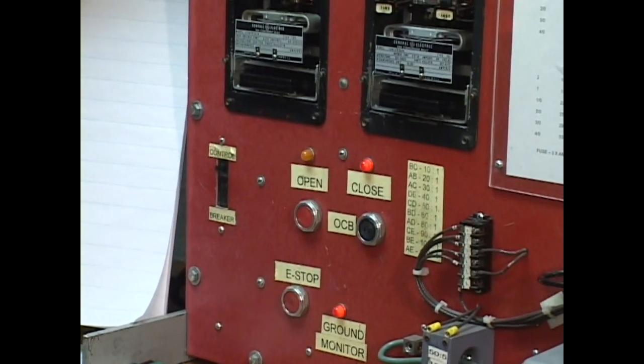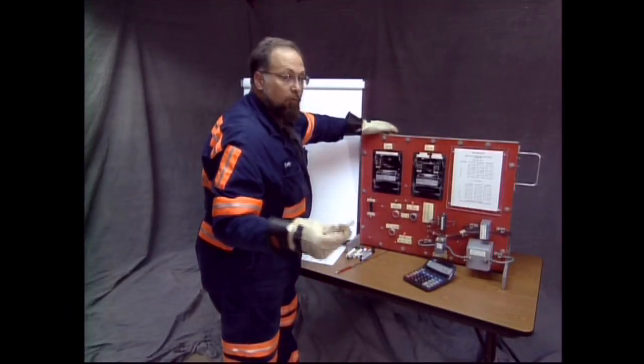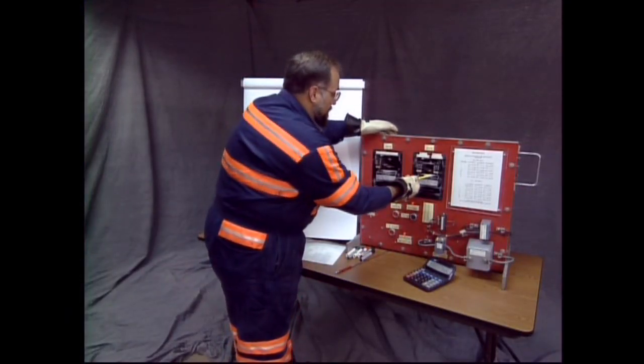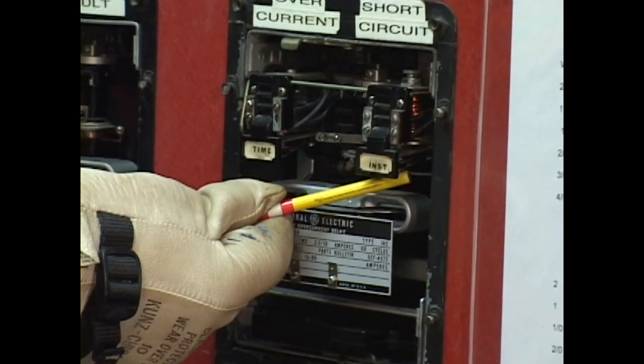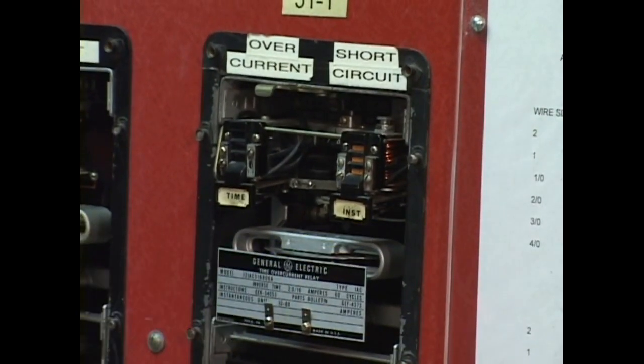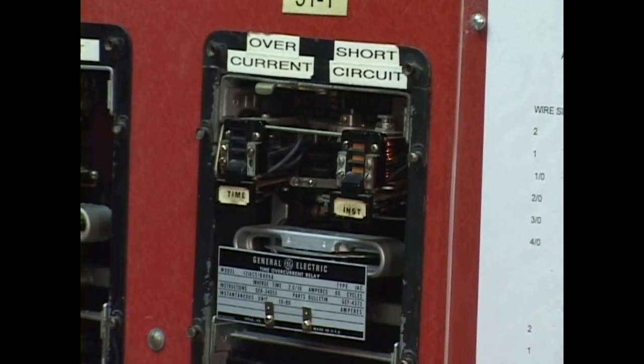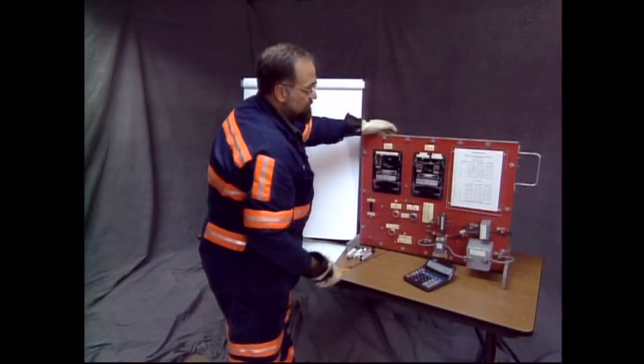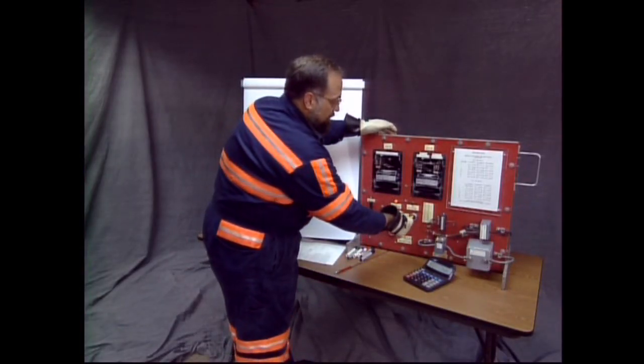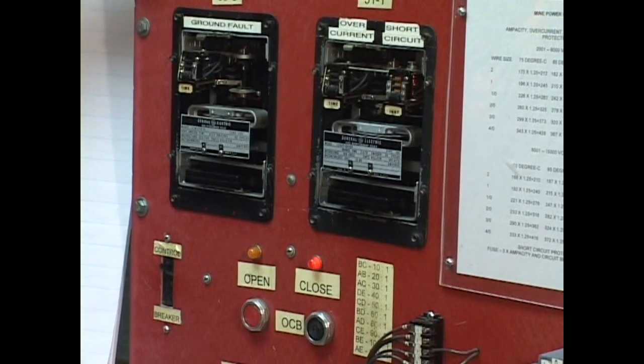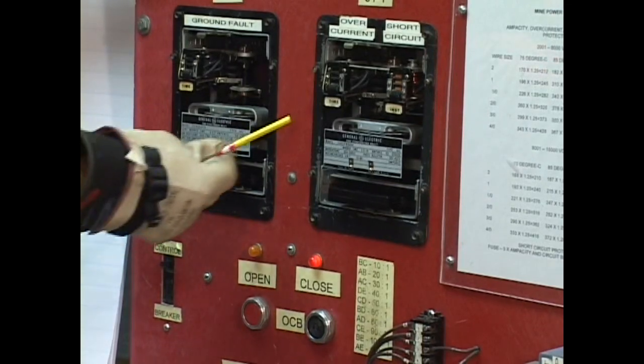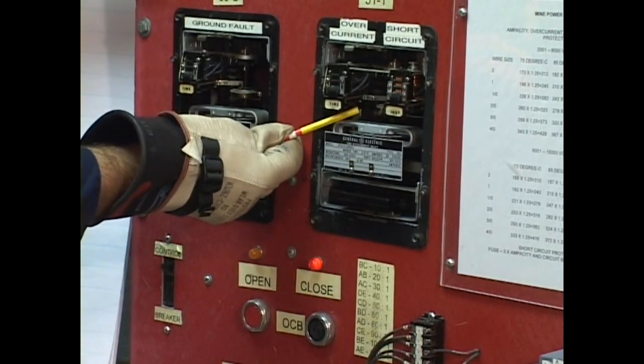The apprentice needs to illustrate. I'm going to manually operate my short circuit relay and gently put the contacts together. And when you do, the OCB opens and a flag shows. All right, you reclose the breaker. I'm going to manually operate my overcurrent relay. Gently raise the contacts and touch.